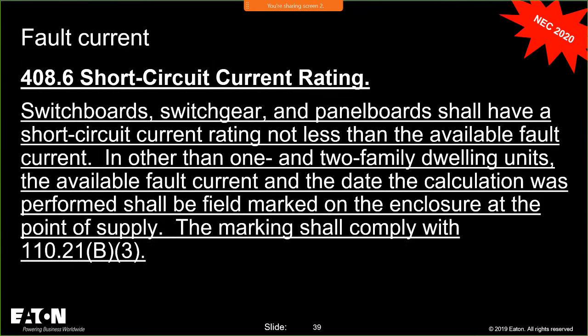The language reads like what you're seeing here. Panelboards shall have a short circuit current rating not less than the available fault current. In other than one and two family dwelling units, the available fault current and the date the calculation was performed shall be field marked on the enclosure at the point of supply. The marking shall comply with 110.21(B)(3).